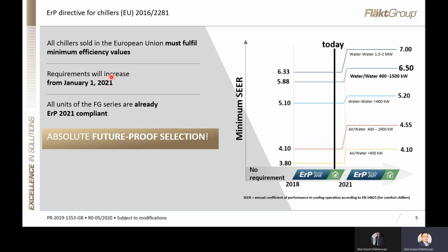All chillers sold in the European Union must fulfill minimum efficiency values as per this. Even after Brexit, apparently, we are going to stick with all these regulations, including the F-gas and ERP directives. So this is mandatory for all chillers sold in the UK. All FläktGroup chillers are already ERP 2021 compliant. So we are absolutely future-proof with the selections we have provided you.